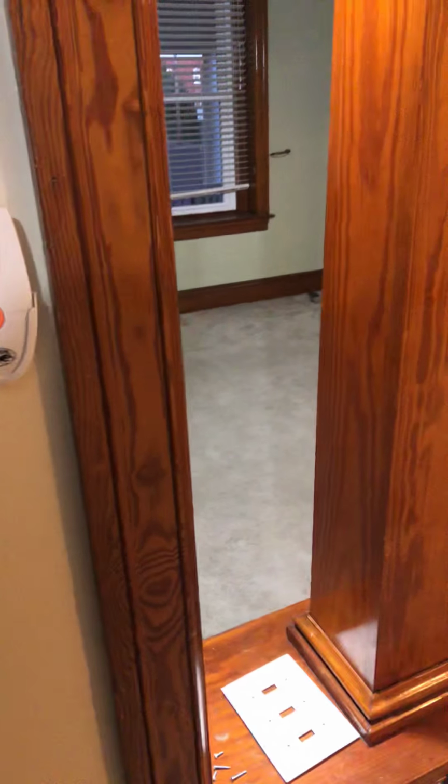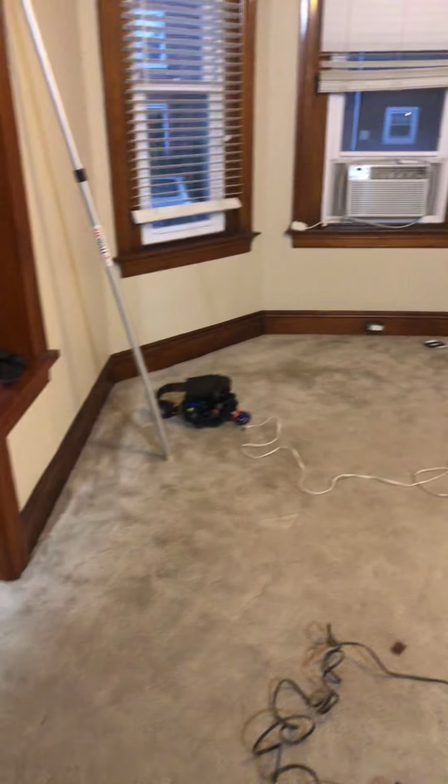When you dim a fan, it builds up heat in the fan because you're restricting the current flow. The motor wants to work, okay? And that motor is gonna heat up. It actually damages the motor. If it doesn't damage the motor, it can do other things. It can burn the motor up, all right?